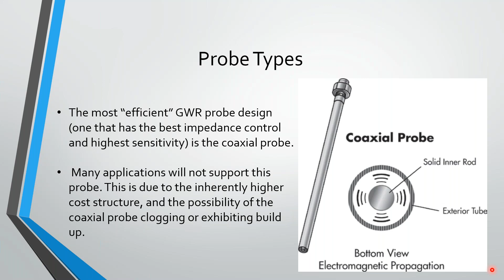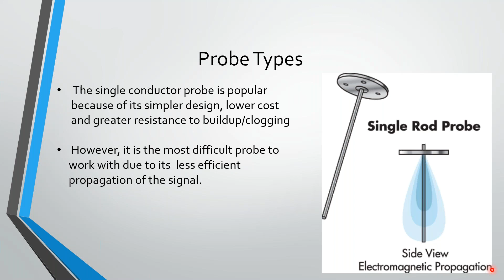So then we go to the single rod. Of course, there's double rod in between there, which I haven't put a picture of. But the single rod is the most popular. It's the least expensive. However, it's the most difficult to set up. Works well, but you're going to be spending a little bit more time during the startup and commissioning of the device. It's going to take you a little bit longer to get everything set just right, and to do the programming in the device to make it work properly.